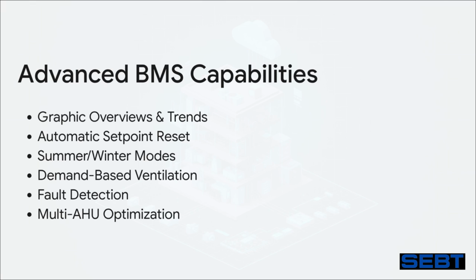The BMS can perform automatic set point resets based on the outside weather, seamlessly executing seasonal optimization and summer/winter modes. It leverages scheduling and demand-based ventilation, so we're only conditioning air when spaces are actually occupied. It even uses all this data for predictive maintenance and fault detection. But most importantly, it allows for multi-AHU optimization, ensuring the entire building is operating in perfect harmony to meet those really strict ISO 50001 energy standards.